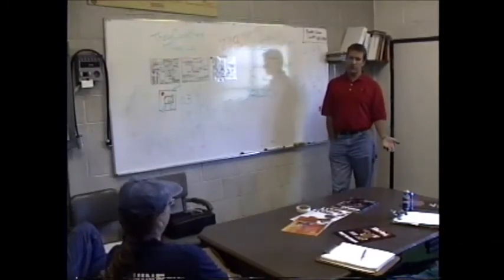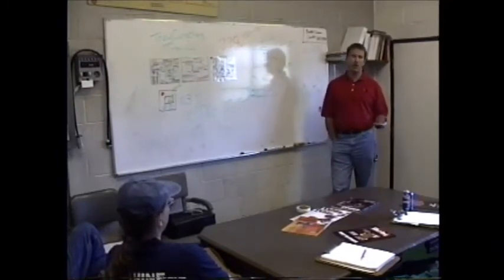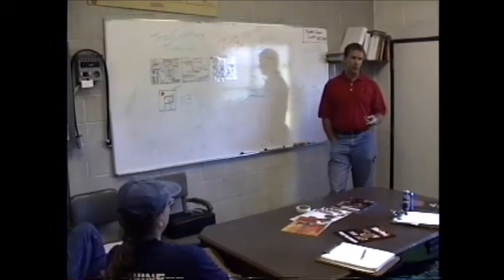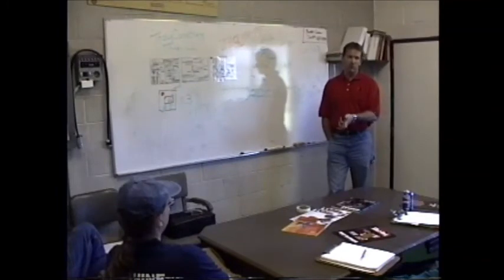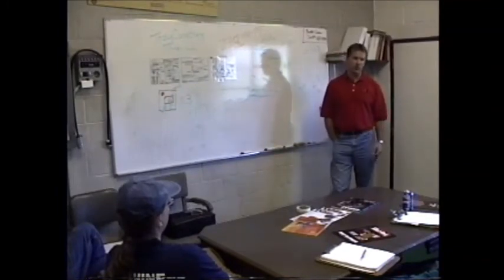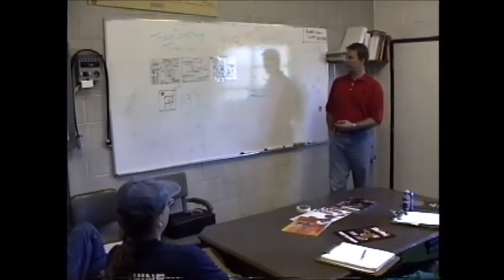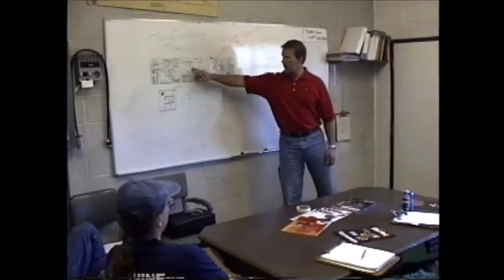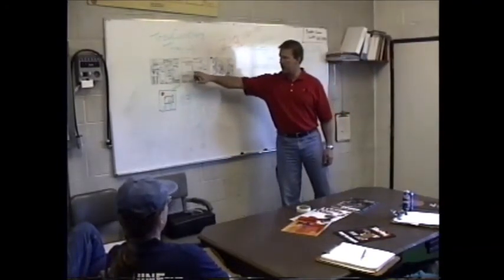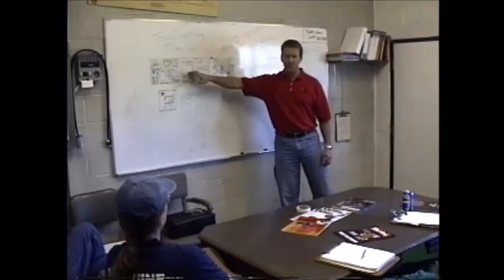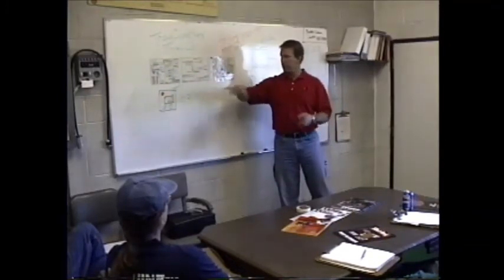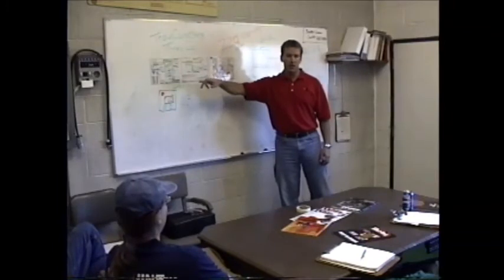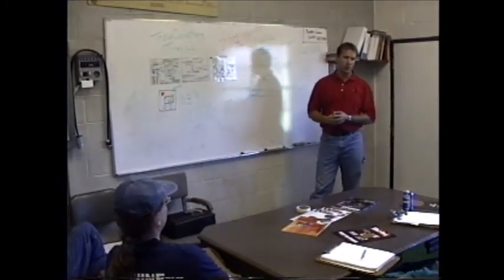That would be your limiting point. At that point, you don't have equal air pressure to water pressure anymore. Right. And you can still pump air at 150 psi into a water stream at 170 psi. You've just got to give it a lot more volume to try to overcome that pressure differential. But if you leave space in the hose, it should still be able to push past that check valve, even though it's got 170 psi coming this way. Because it's CAFS, because it's a compressible medium, you should be able to force air in there, even at a lower pressure than what the water and foam is at.